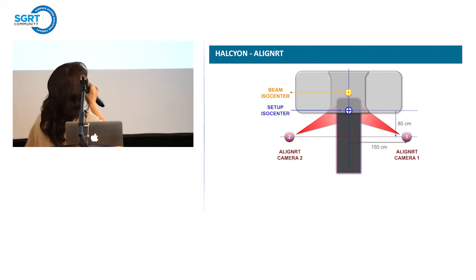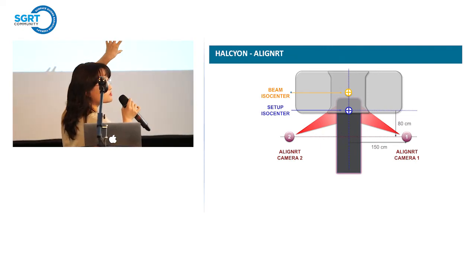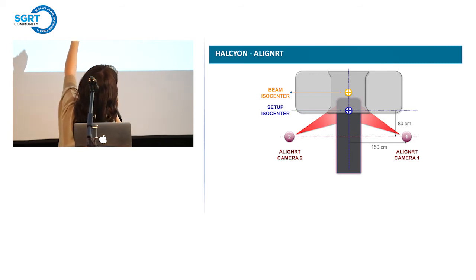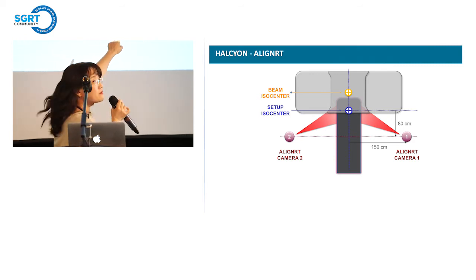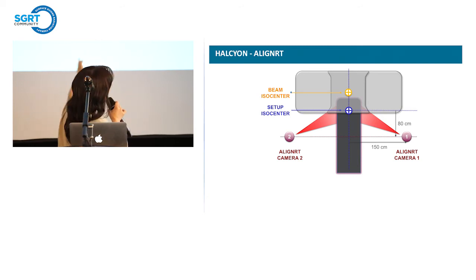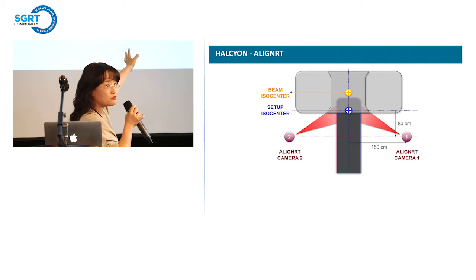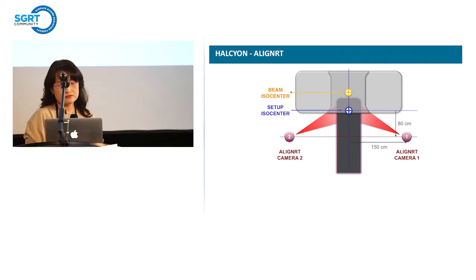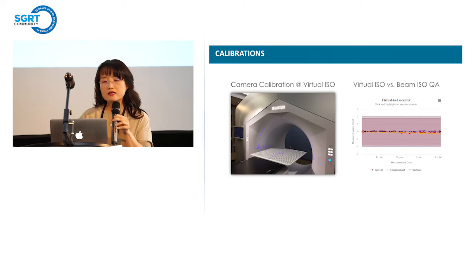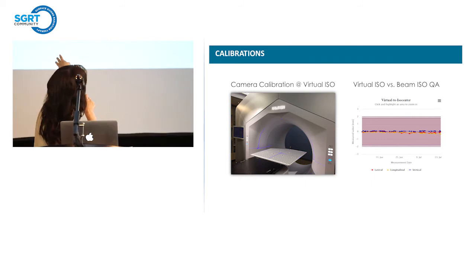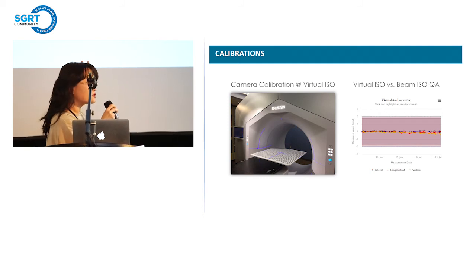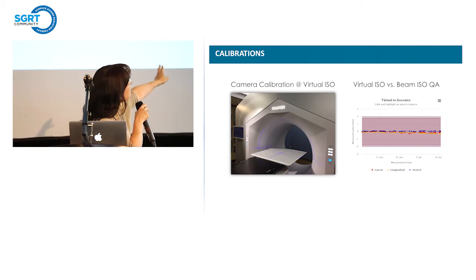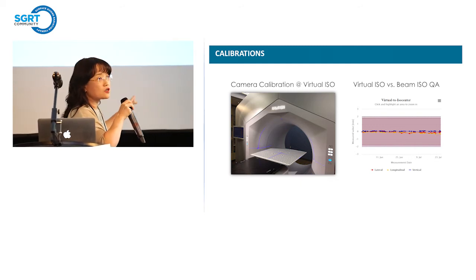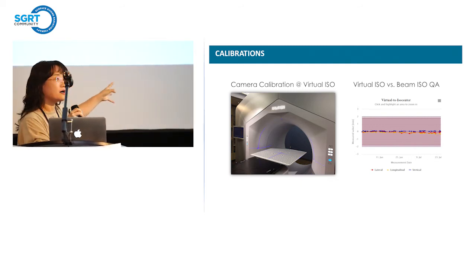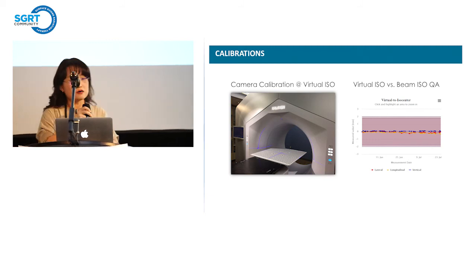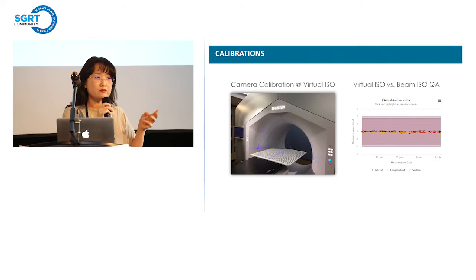So this is our current layout, from top to bottom. On the Halcyon machine, there's the beam ISO, and there's a setup ISO, actually called the virtual ISO. The two camera systems are looking at the virtual ISO right now. The cameras are calibrated to the virtual ISO like this, and we align the laser in the virtual ISO calibration. The virtual ISO is QA'd by the MPC, virtual ISO versus beam ISO. We keep tracking with the online QA system how well they match, usually within a 0.2 millimeter range.